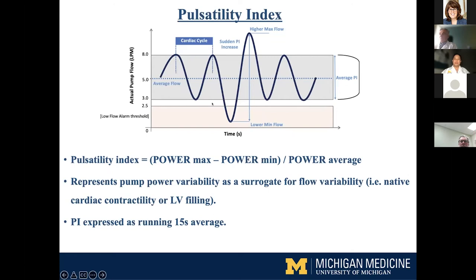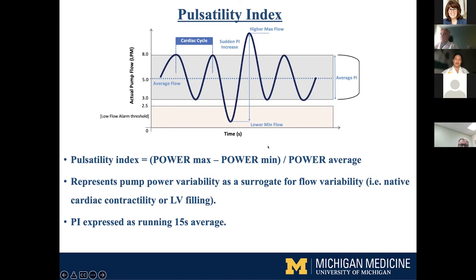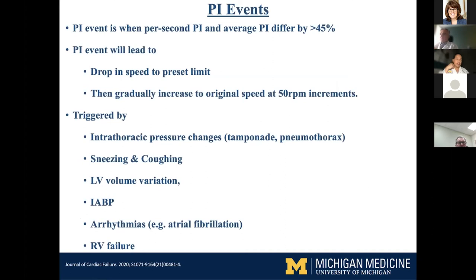Pulsatility index — what does that mean? It's really measured as a 15-second average: maximum power minus minimum power over average power. Since power is a surrogate for flow, it's essentially maximum flow minus minimum flow over average flow during that period. Any variability in that flow can be seen as a PI event, due to changes in LV filling, native cardiac contractility, arrhythmias, and so on. Any drop in flow can be interpreted as a PI event. If your PI varies by greater than 45%, it's logged as a PI event.